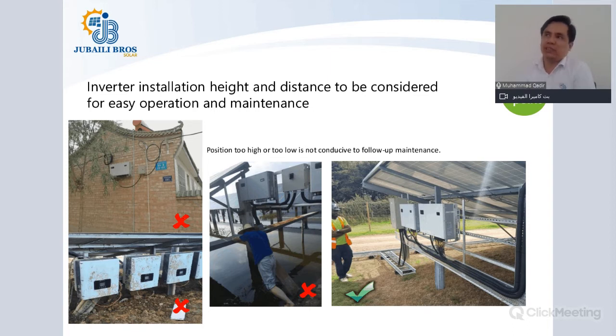There could be project scenarios where, due to space constraints, you might be installing the inverters at a different height. That is also feasible, that is also okay, but you just need to consider the spacing required as per the Huawei user manual. If you are using a zigzag type of installation, there is a special guideline for that as well, which is mentioned in the Huawei user manual.